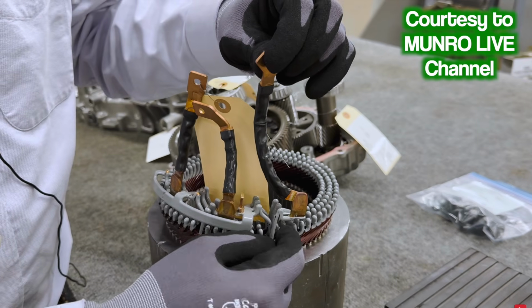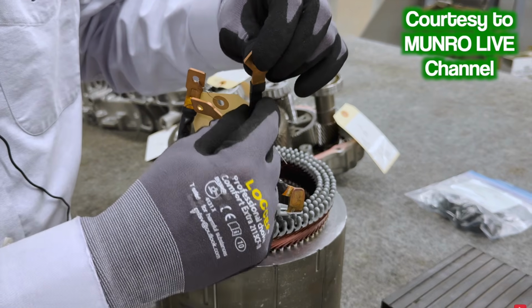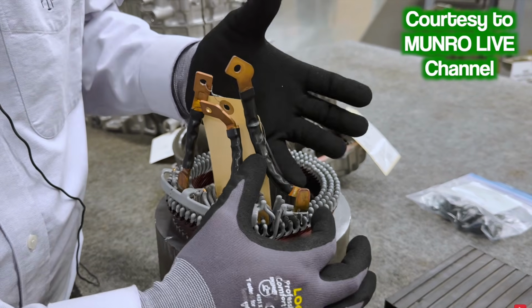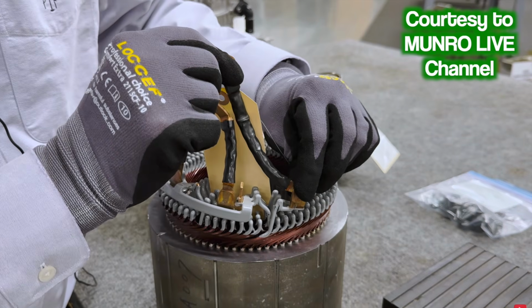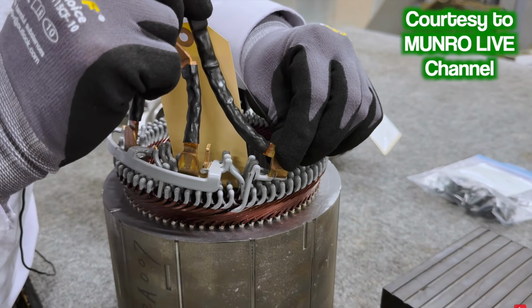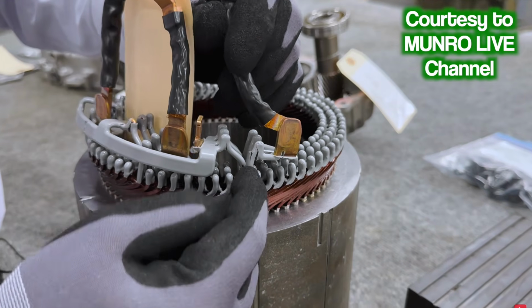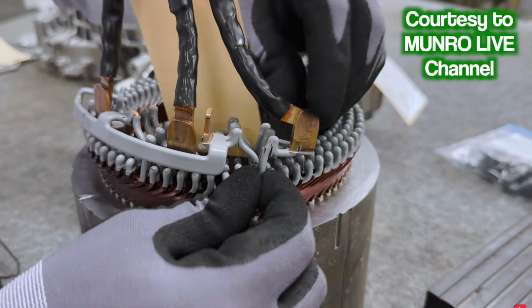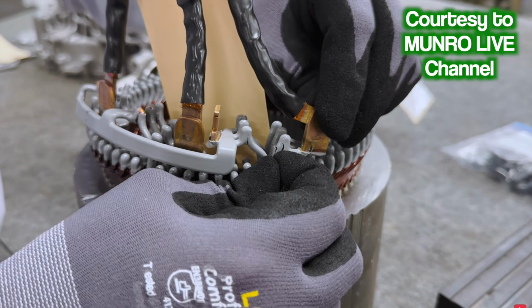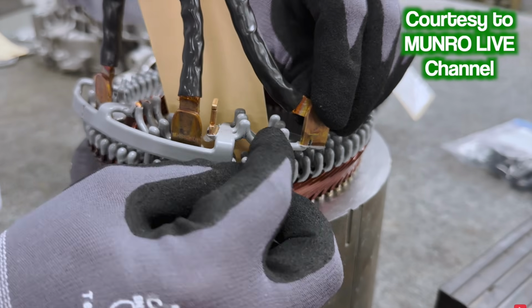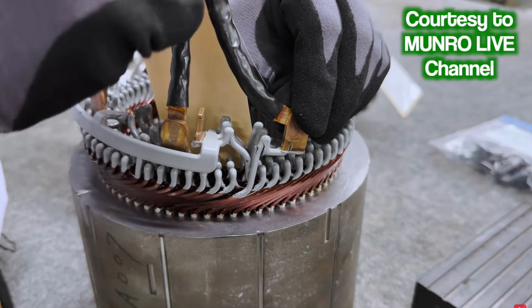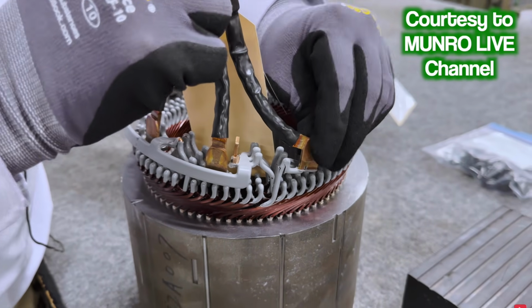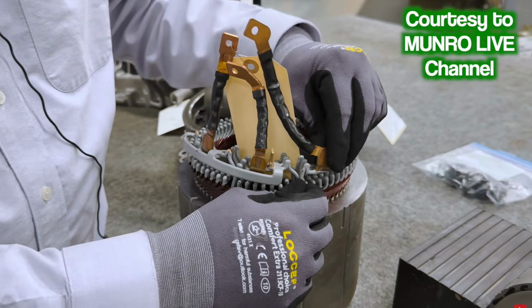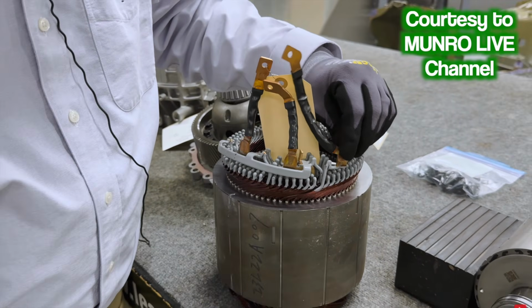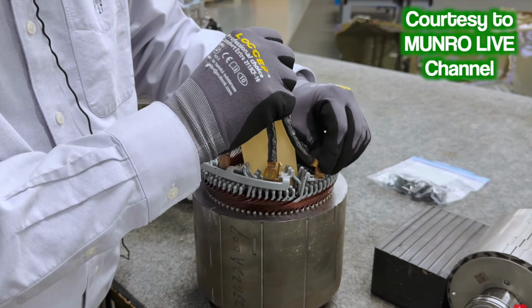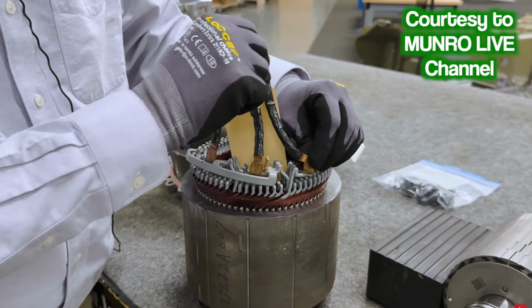And when it heats up, the copper expands. And when the copper expands, it pushes down on this. And this also expands, so these three push up. So this is up and this is down, and it flexes that joint. Then you turn it off, it cools back off, and flexes the other way. Over time, it flexes back and forth every time you turn the motor on and off.